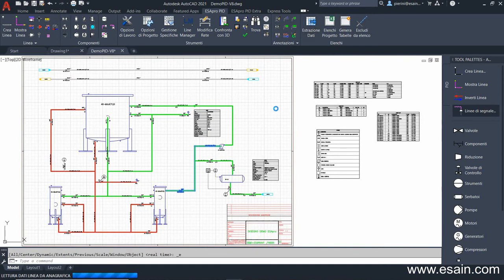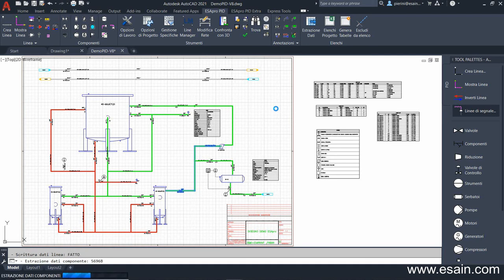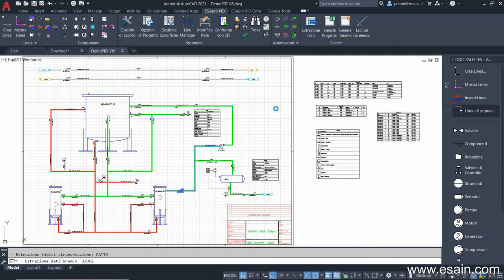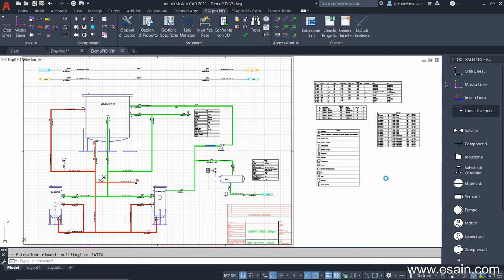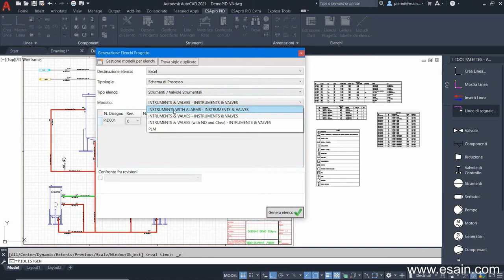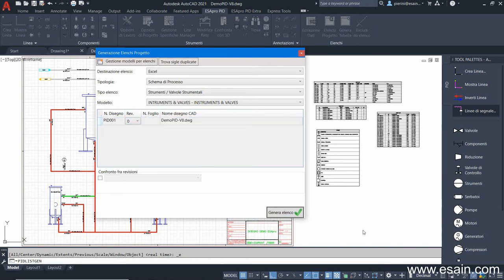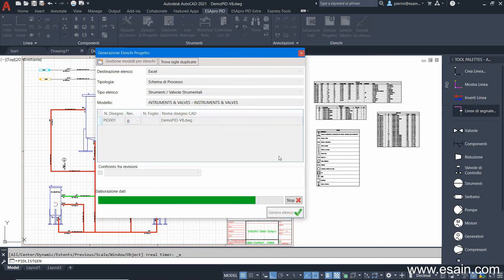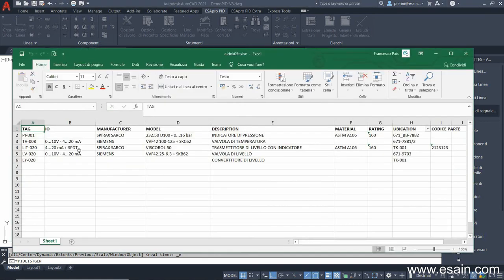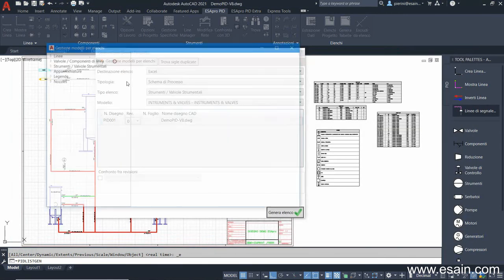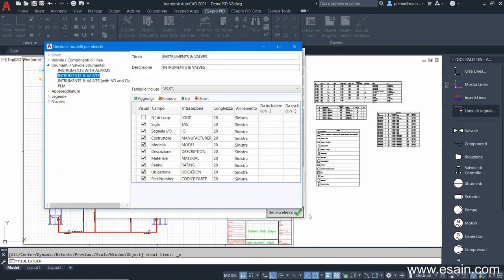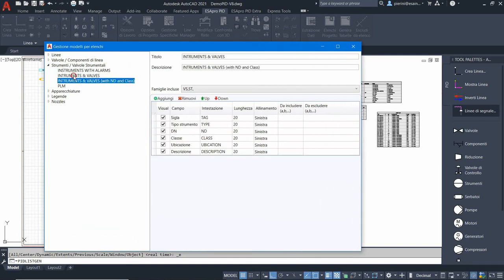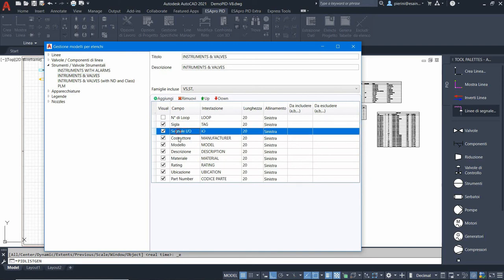We have graphically changed the scheme, but it's only with the data extraction command that the database is actually updated. At this point, the data will also be available to other ESApro modules: 3D piping and instrumentation. The tables already inserted in the drawing are automatically updated. And with the project lists command, it is possible to export the data of the tables into an Excel spreadsheet. Here I choose the list template, the drawings I want to extract and click on generate list. An Excel sheet is generated with a structure that I've previously configured. The configuration of this structure can be done through the list templates management dialog. Inside this dialog, it's possible to create a new list template and select the fields you want to show, specifying for each one the header and the sort order.